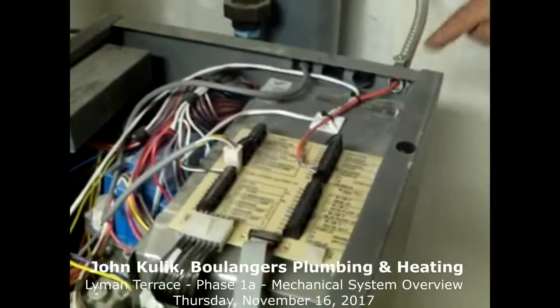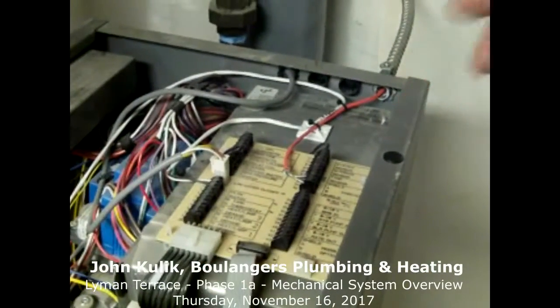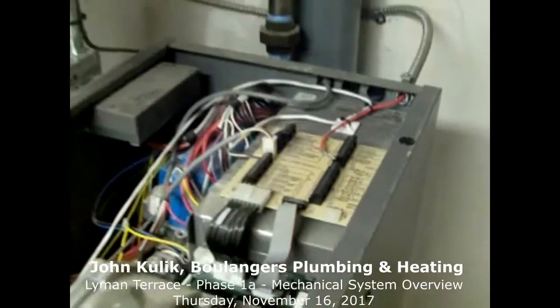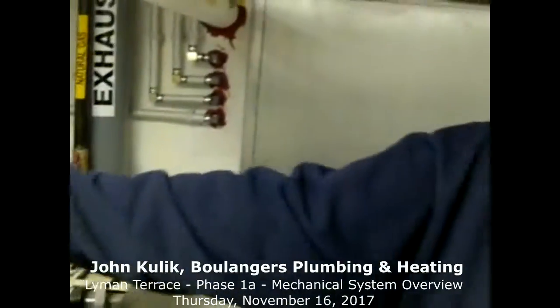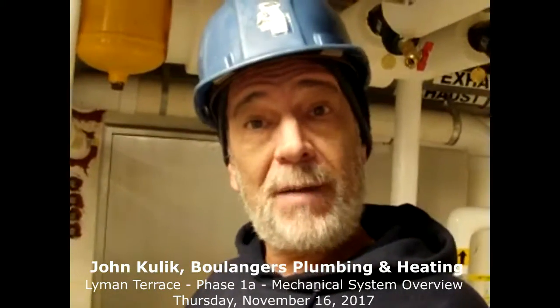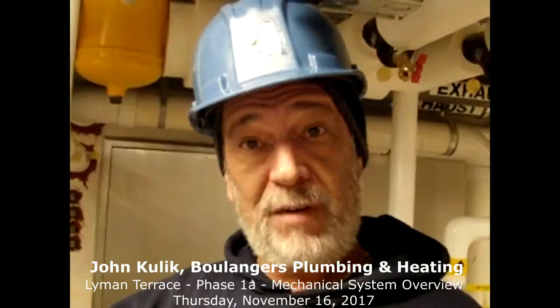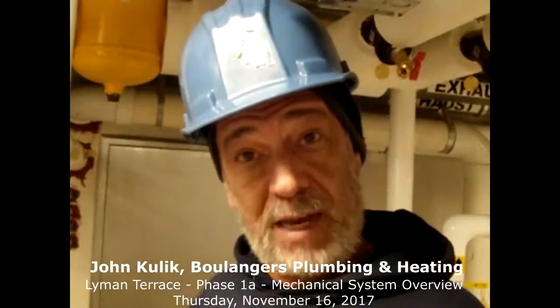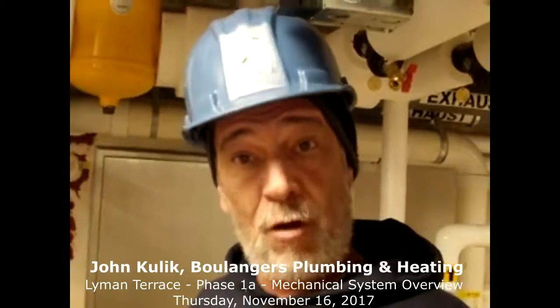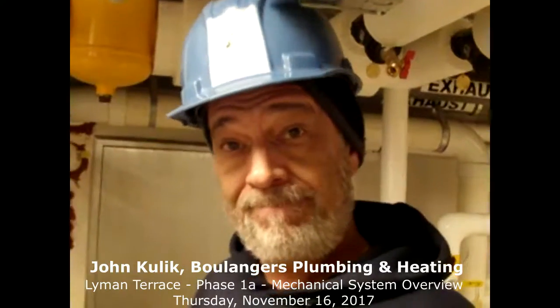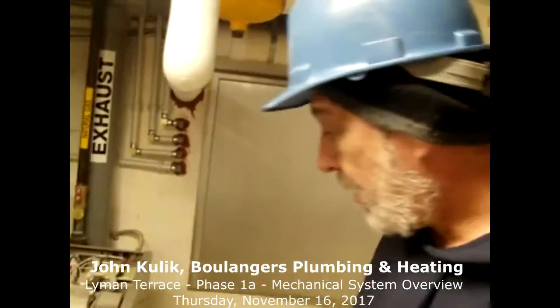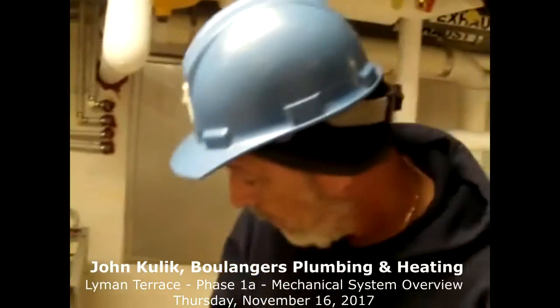And this is the communication link between the 2 boilers. This is the lag boiler. That's the lead boiler. That one there takes all the inputs from everywhere, outdoor temperature, loop temperatures and all, and then tells this one whether to run or not. If the lead boiler fails for any reason, we'll automatically fail-safe switch to the second boiler to take over its duties. Okay? Nice. But again, back to the cleaning.